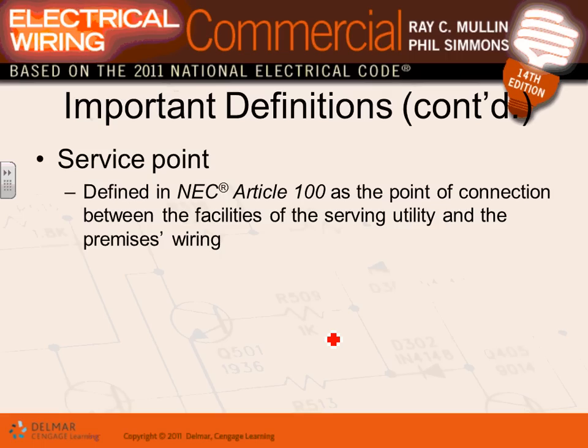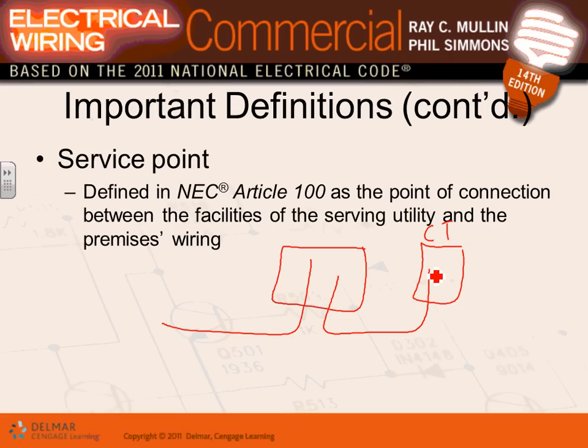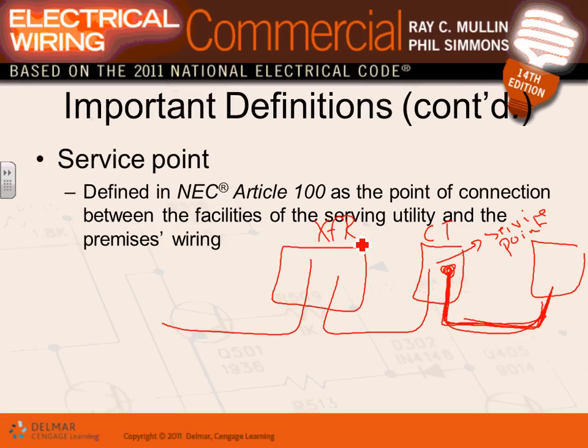This is the single most important thing probably, guys. Here's my transformer here. Here's my CT cabinet. I'm coming from here and from here to the CT cabinet, from here out into my building. So Adam, this cable here is service entrance conductor coming to my building, and this point here is called service point. Can you guys see that? This point is service point, which means from here to the building I own and operate, from here to the transformer, XFR, the utilities own and operate. Any comments, guys? Any questions about service point for the utilities? Typically, the CT transformer, Adam, for a commercial building is your service point.